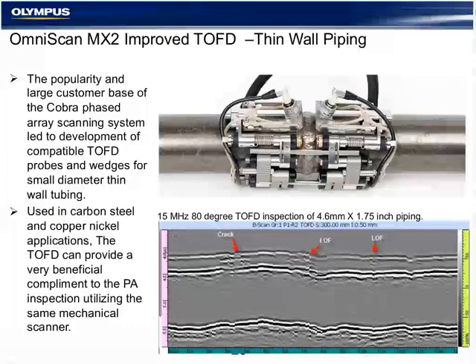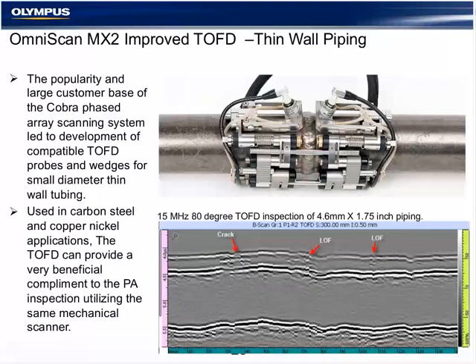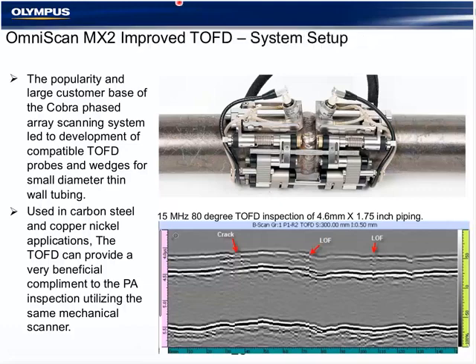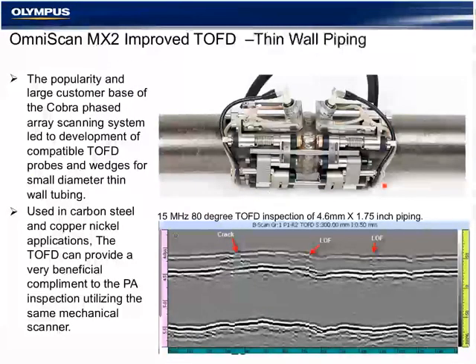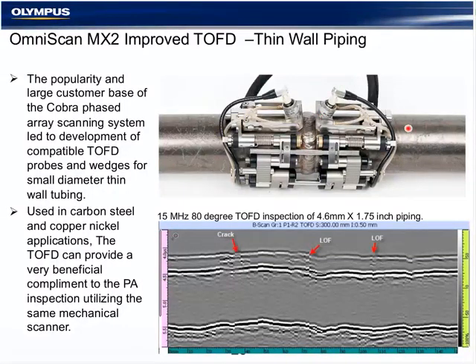Improved TOFD for the MX-2 also includes probes, wedges, and mechanics for components that were traditionally too thin or too small in diameter to inspect. We're having success now with higher frequency, small diameter, thin wall components. In this case, we see an 80-degree TOFD L-wave inspecting a 1.75-inch diameter, 4.6-mm thick component using the COBRA scanner system.